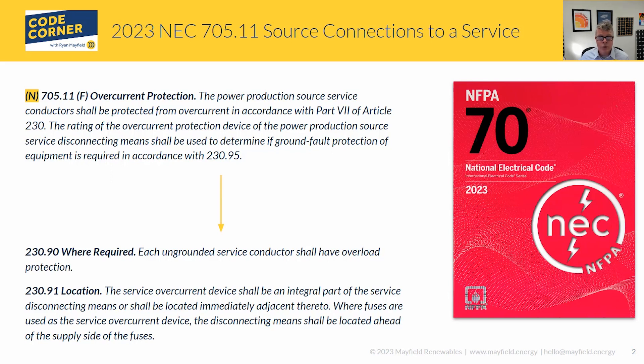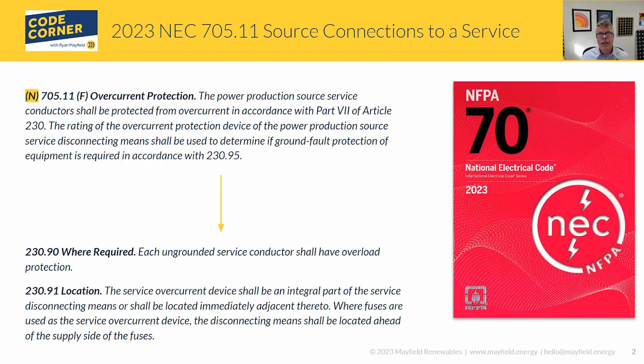If you have the handbook or NFPA link enhanced content, Section 230.90 explains that ground fault protection and short circuit protection is provided by the installation of the service conductors themselves, and that the overcurrent device is providing purely overload functionality. Moving on to 230.91, the overcurrent device shall be integral to the service disconnecting means or located directly adjacent to it. If fuses are used, the disconnecting means must be ahead of them so the fuses are de-energized in the off position.